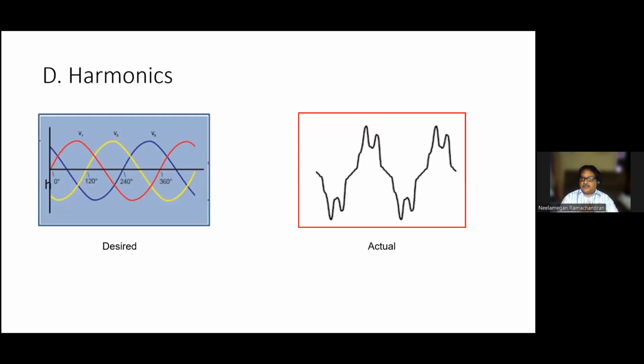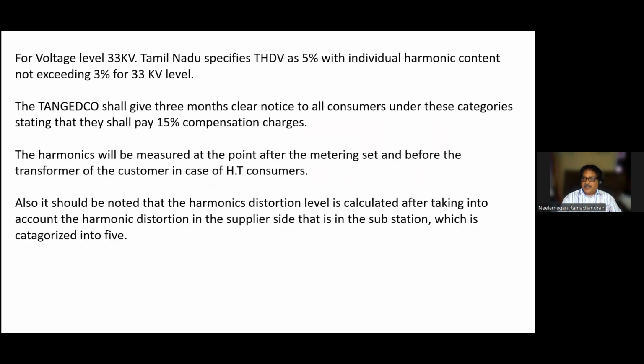Then comes the most dreaded subject of every engineer, I think: harmonics. Suddenly we find a breakdown which is not expected at all. The culprit will be harmonics, which cannot be measured easily and cannot be easily pointed out. So they have now come up with a penalty for this, for 33 kV and the whole system. And shortly, I think, for 11 and 22 kV also this will come. I think they have already done it, or they are on the verge of doing this.